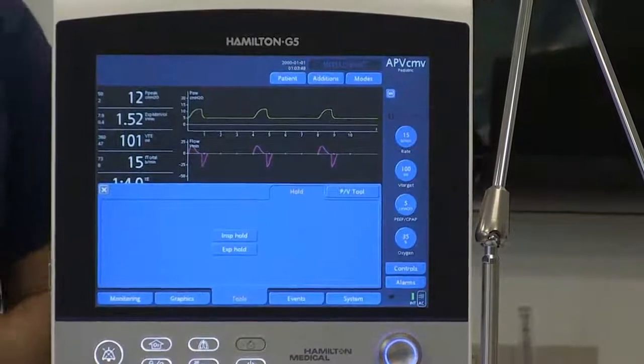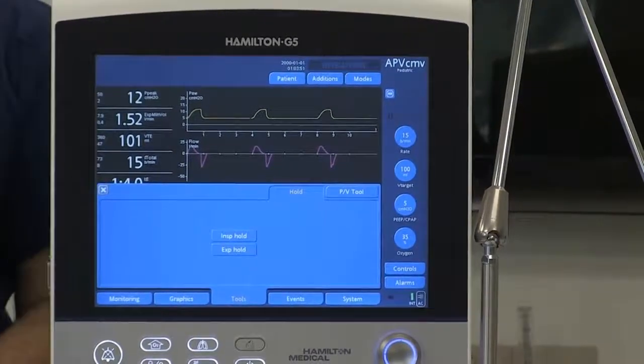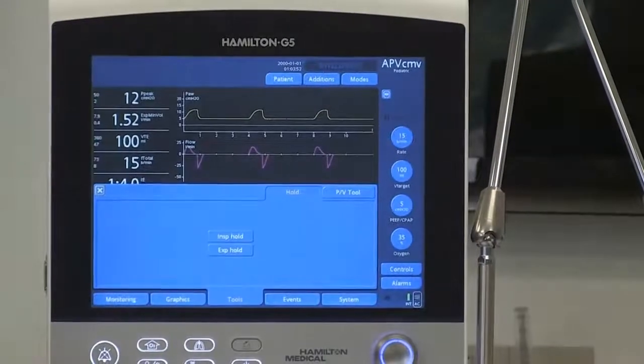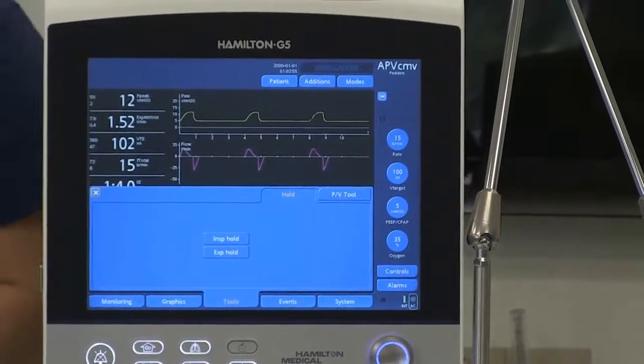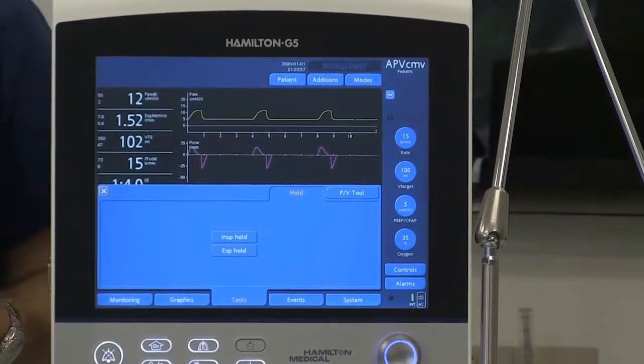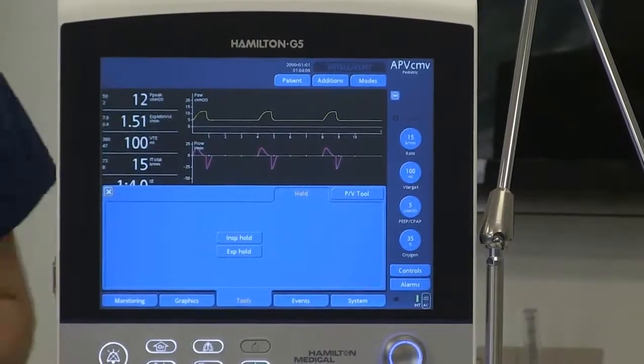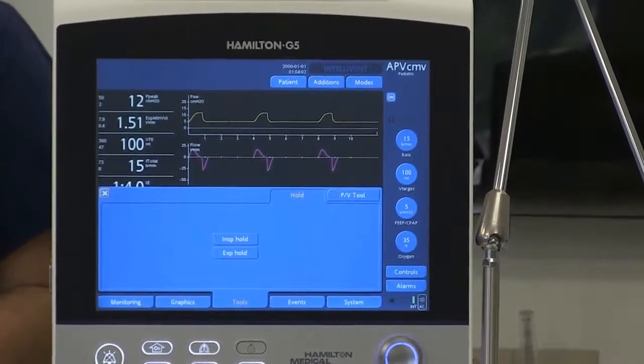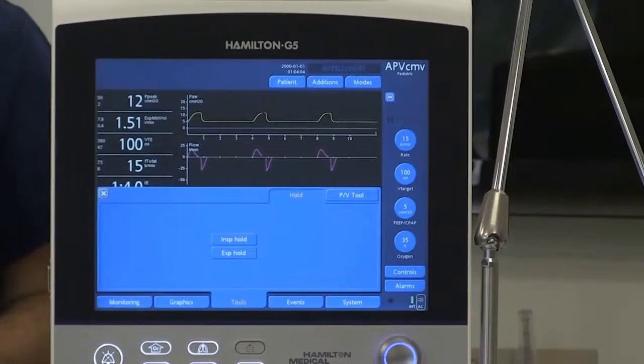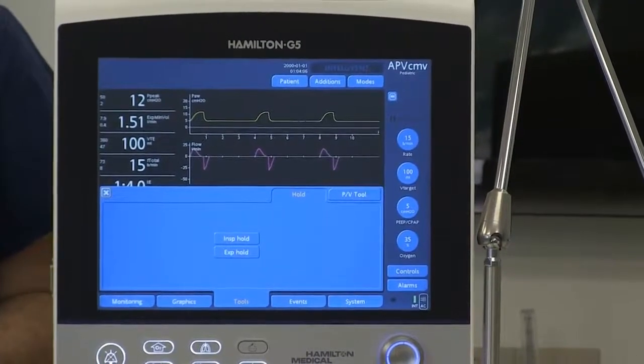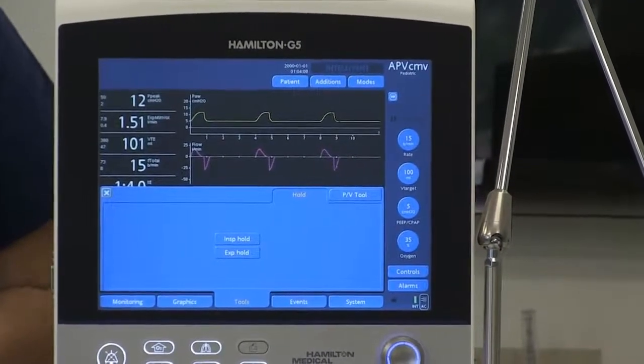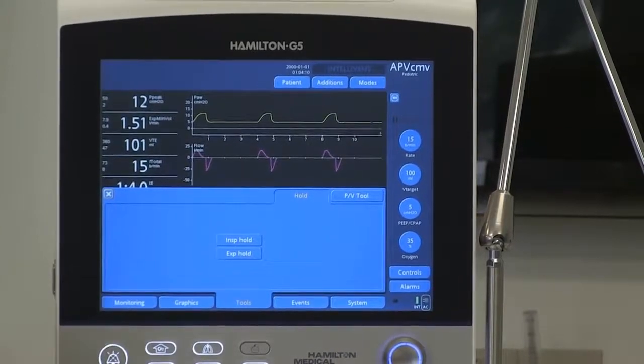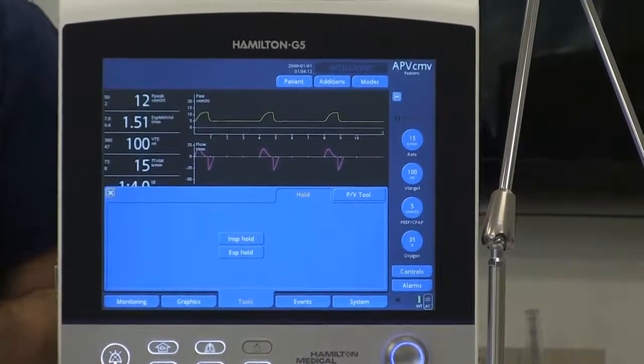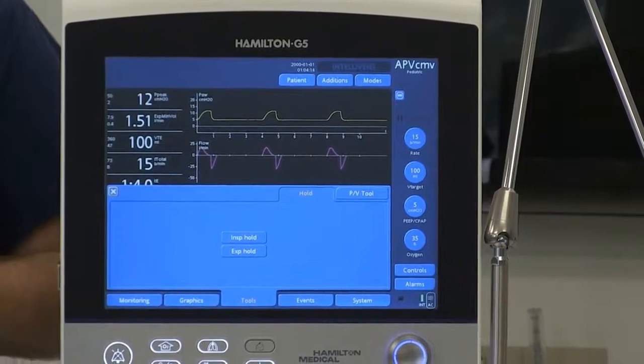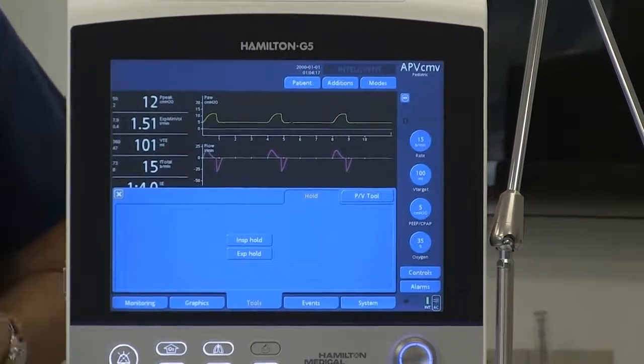In the tools section, this is where you'll find your inspiratory hold and your expiratory hold, along with a unique Hamilton feature called the PV tool, which allows the clinician to give the patient a very slow flow inflation up to a peak pressure, and then a very slow flow deflation to a minimal pressure, giving an accurate picture of the lungs, allowing you to set PEEP and an overdistension pressure.